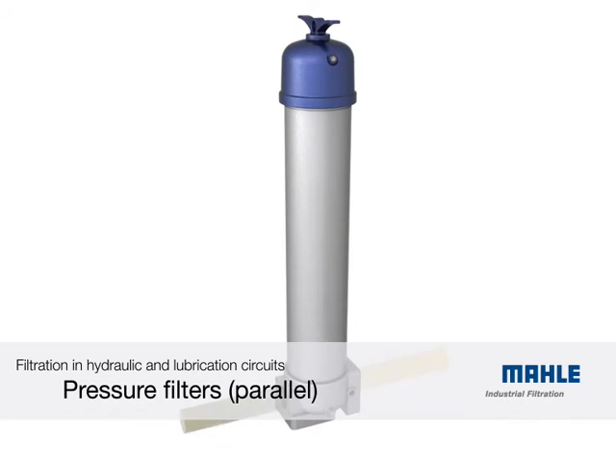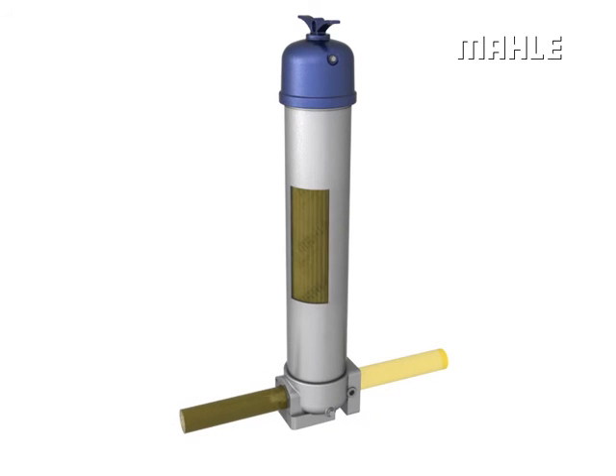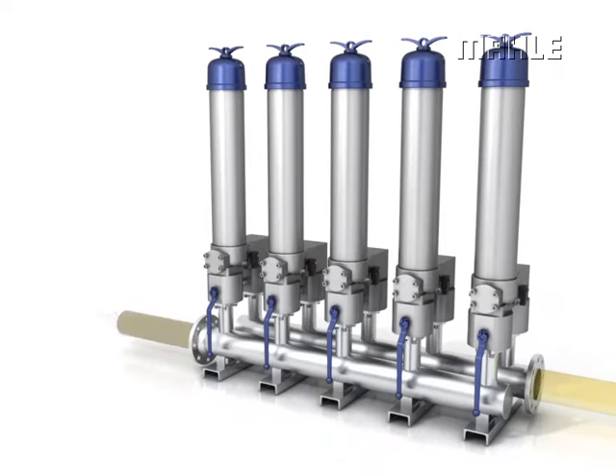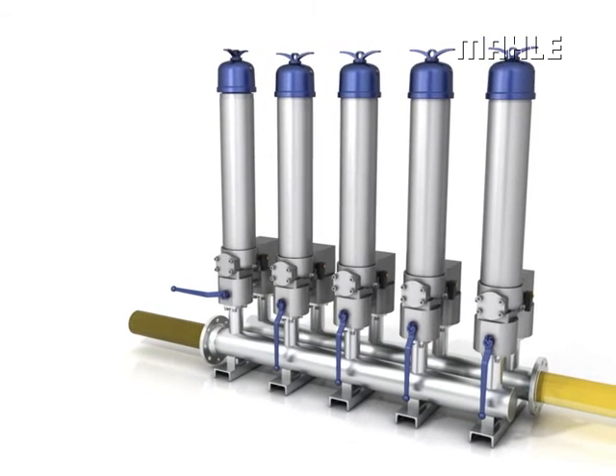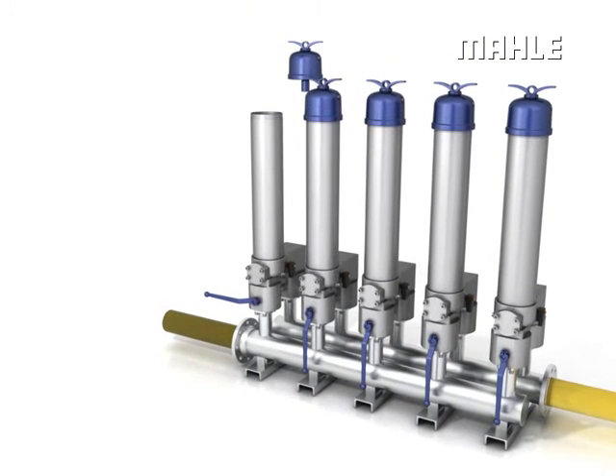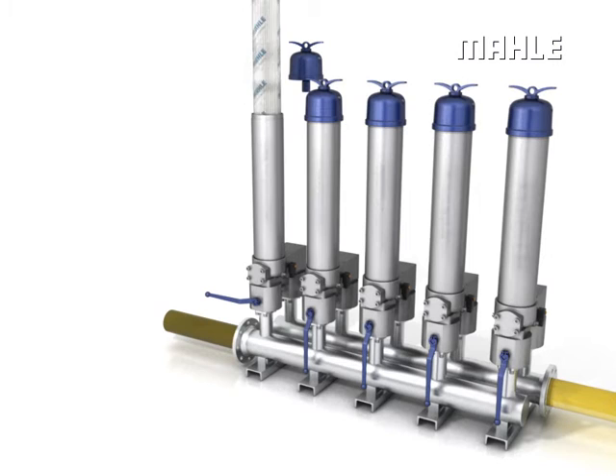Parallel pressure filters: a modular, easy-to-maintain filter system is available for filtering large amounts of oil. The filter can be used individually, or several filters can be linked in parallel. A single shutdown feature enables operation without interruption. To replace the filter element, unscrew the cover of the filter housing, pull the element up and out, and place the new filter element into position.